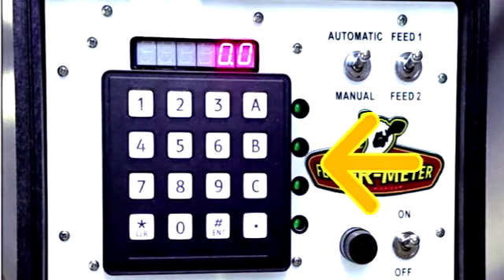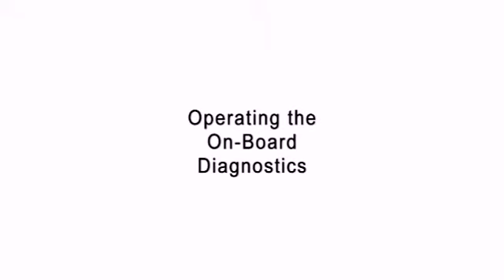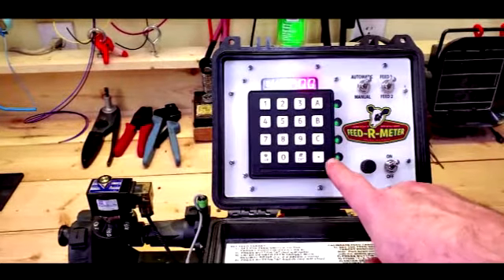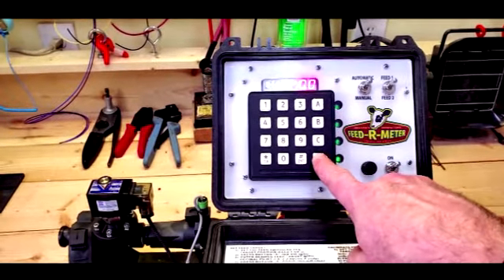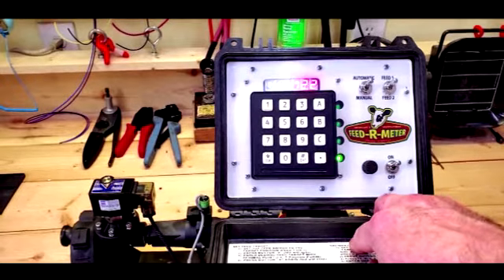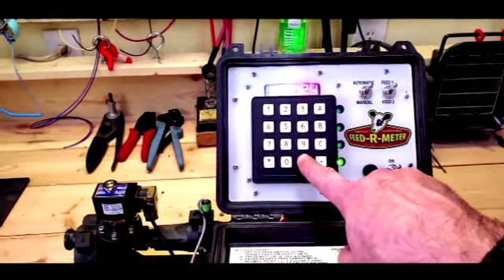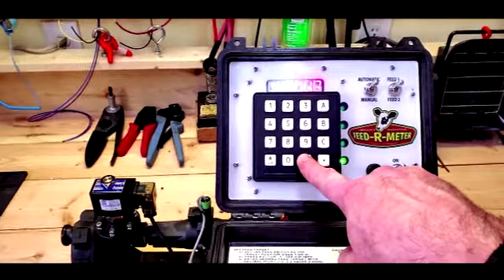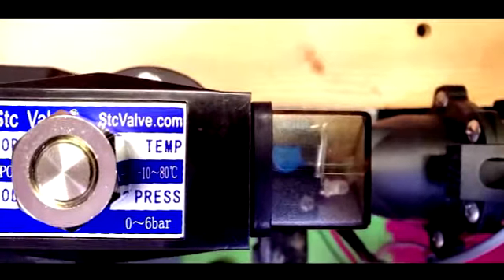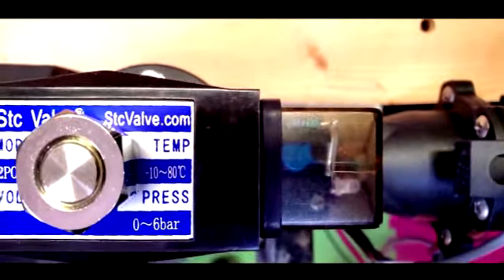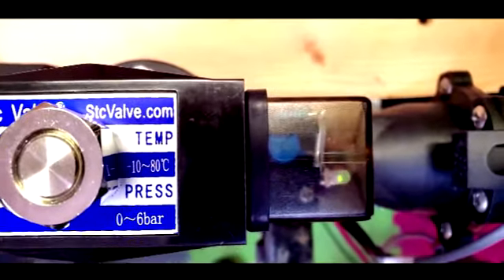Before you feed, the easiest way to see how the system is operating is to make sure your wiring is okay and enter onboard diagnostics, which is a little dot button on the right. You'll see your line voltage comes up on the screen. As you hit the hashtag button next to it, that turns the solenoid on and off on the flow meter. You can see the light illuminates inside the housing and you'll hear a click.